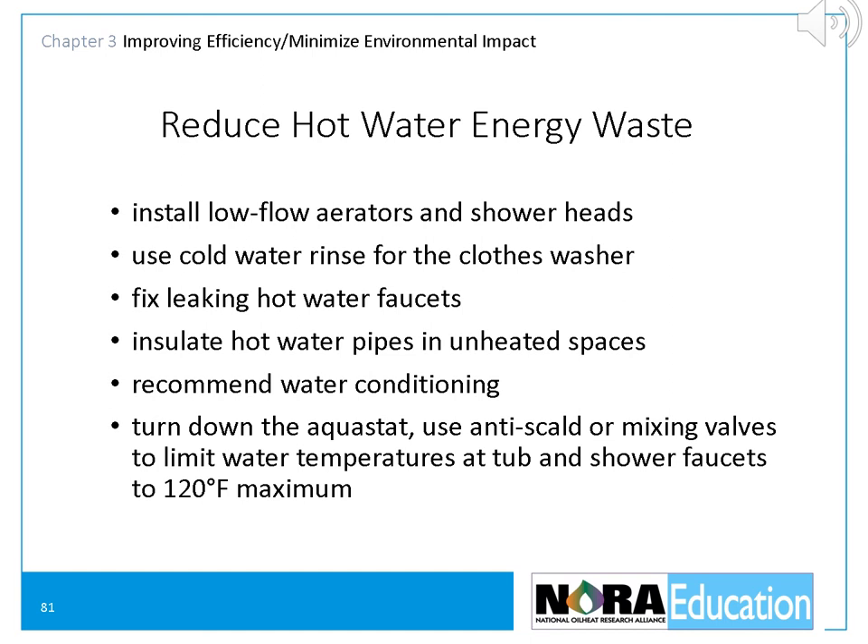The question of which water heater is best depends on the situation. For a furnace or a large hot water demand relative to the heat load, the best option is the direct-fired oil-powered water heater — the high-recovery king. If the customer has a reasonably efficient boiler, they are better off with a storage tank indirect water heater because there's only one burner heating both the space and water. The best system of all is an integrated boiler with an indirect water heater and a storage tank system.